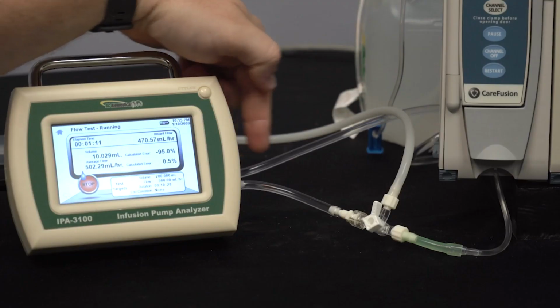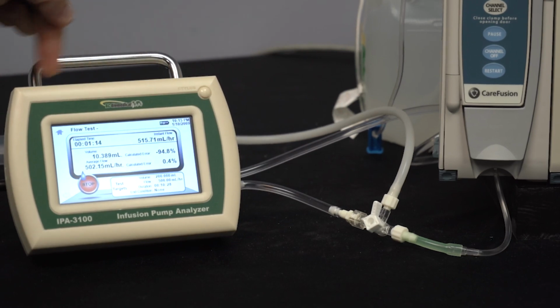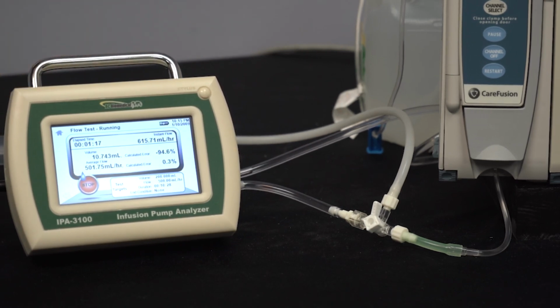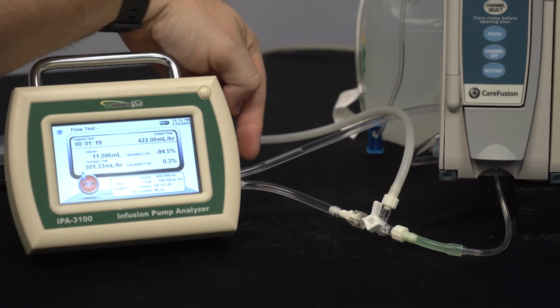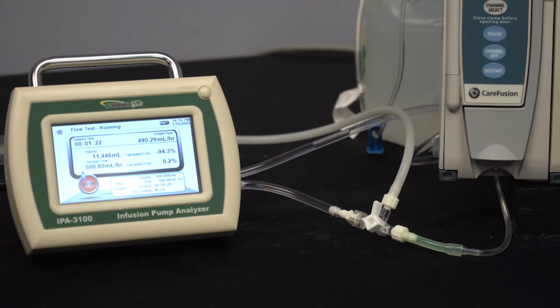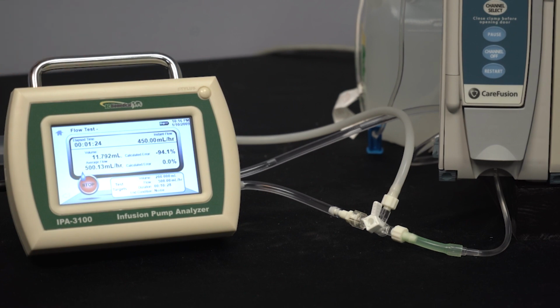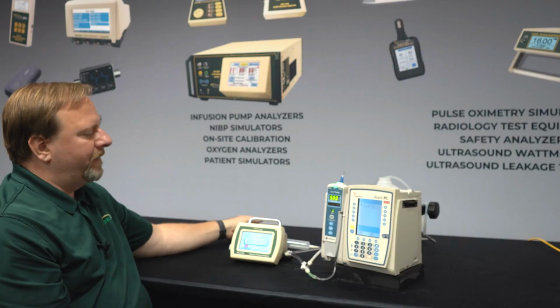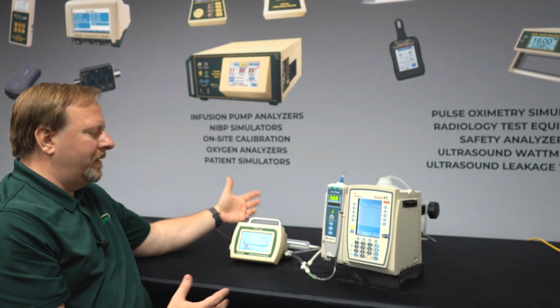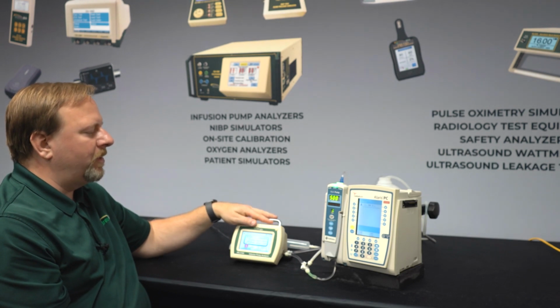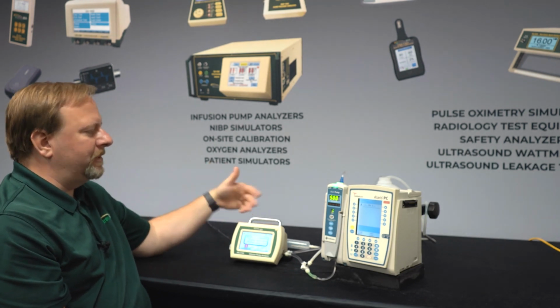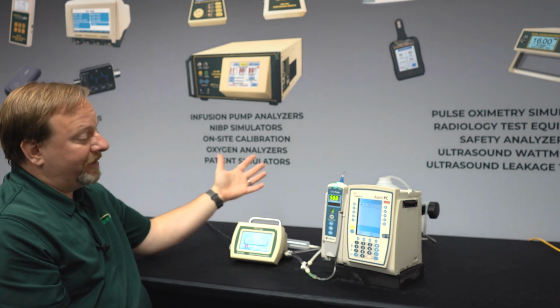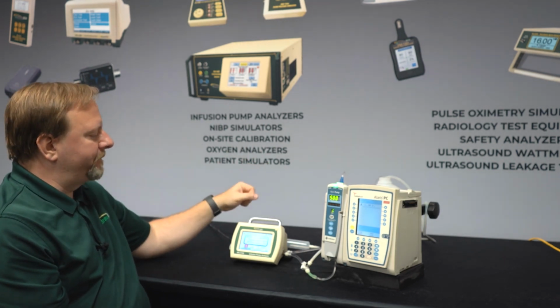We've seen a lot of air, several large bubbles come into the system. They're working their way through the internals of the IPA 3100. And here we can see they've worked their way out. So the test has continued. It hasn't affected our measurements, hasn't affected the readings, and more importantly, it hasn't canceled the test. So that's something we can offer as a feature that we've mentioned in the past in other videos. We've mentioned that we don't have any effect on bubbles. Bubbles don't affect our tests, and so here we can see that in action. That really is the case.